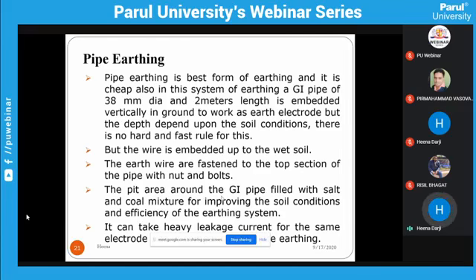So if your soil resistivity is high, you have to use 40 mm dia and 3 meter length, as well as 100 mm dia and 5 meter length embedded. But the pipe is embedded up to the wet soil. The earth wire is fastened to the top section of the pipe with nuts and bolts.